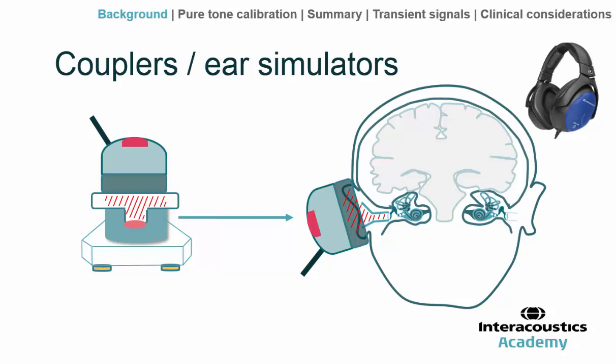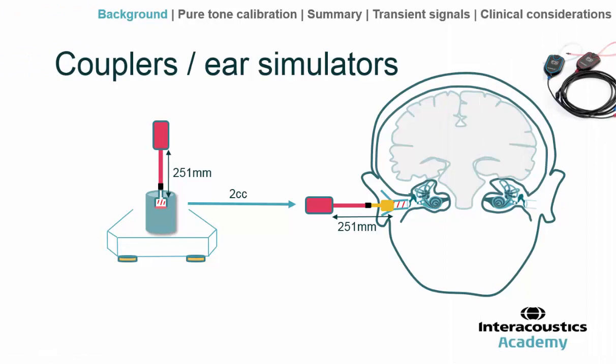For the circumaural headphone, which encapsulates the whole pinna, the residual ear canal volume is somewhat greater than 6cc. We take the same coupler but apply an adapter to simulate that increased volume. For insert-style headphones, the sponge is inserted into the ear canal so the residual volume is less than 6cc — we would typically use a 2cc cavity for inserts.